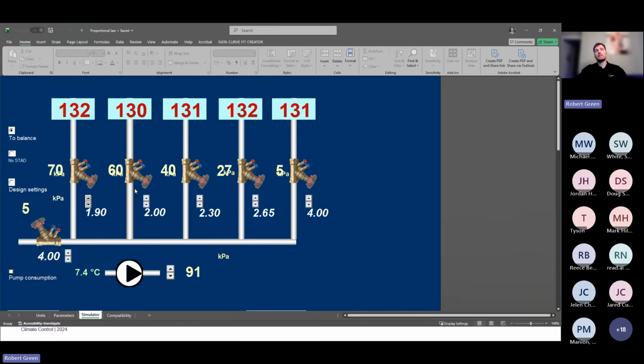Now, this is a pretty simple system. Directly, my pump is serving this one system. So actually, I can just reduce proportionally by reducing my pump head. If we reduce my pump head until we get 100%, turn on my little pump consumption, as if by magic, as you may well have expected, we are now back to 100%. My pump has been set and optimized. And you'll notice this valve here is actually fully open because we've done my final setup on the pump.